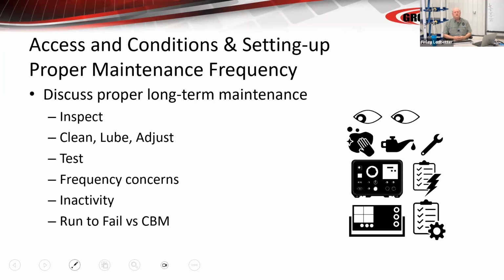Frequency concerns, how often should we come do this? Inactivity, how long has the equipment been inactive? How long have the breakers and relays been sitting there inactive? They've not been exercised, they've not been opened, they've not been closed. There's also run to fail versus condition-based maintenance that has to be considered. If this equipment is in very nice, clean, modern shape, it's very clean, it's in a pressurized room, it had acceptance testing 5 years ago, it all came through, every squawk was corrected, maybe you run a little longer, maybe you don't. These are concerns that you have to take up with your customer. I know on this webinar, there are a lot of users. I went through the list earlier today. There are a lot of petrochem, a lot of heavy industrial users. And this is very critical because I know you're being pushed to reduce the maintenance dollars, but bad things happen.